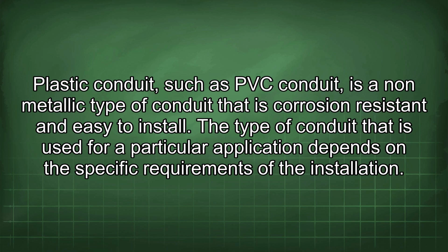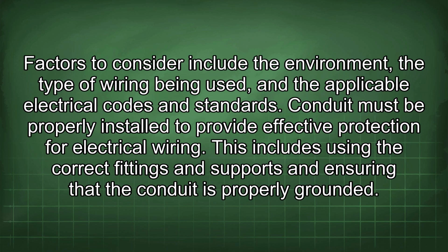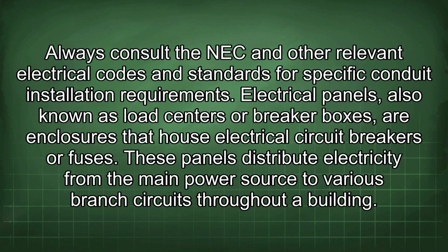The type of conduit that is used for a particular application depends on the specific requirements of the installation. Factors to consider include the environment, the type of wiring being used, and the applicable electrical codes and standards. Conduit must be properly installed to provide effective protection for electrical wiring. This includes using the correct fittings and supports and ensuring that the conduit is properly grounded. Always consult the NEC and other relevant electrical codes and standards for specific conduit installation requirements.